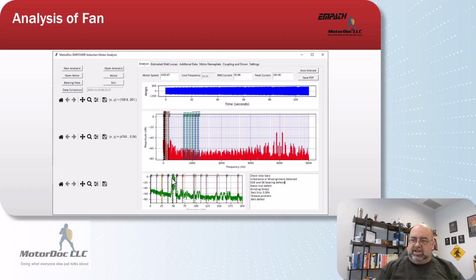But what we had to do in the algorithm is eliminate the extra peaks. Now, because we had the extra peaks and the problem they had, they thought they were going to have to make major changes to their system. All it turned out to be was making a slight adjustment to the VFD, turning the gain down a little bit, and a couple other adjustments, and the problem went away.